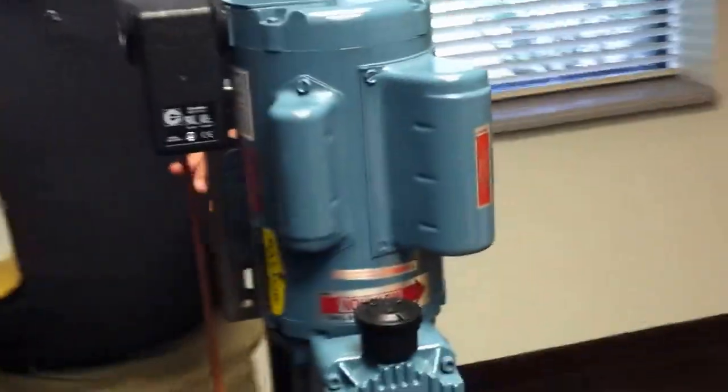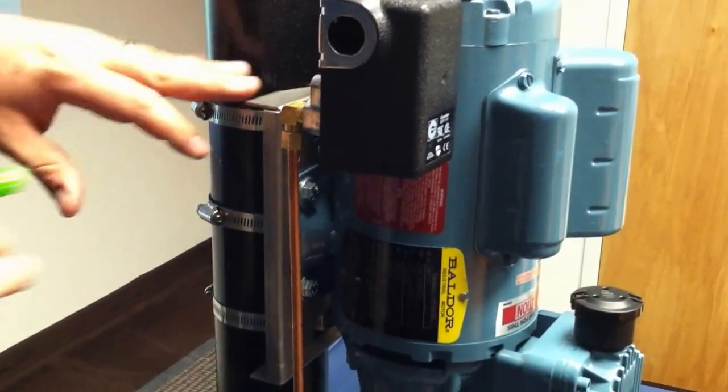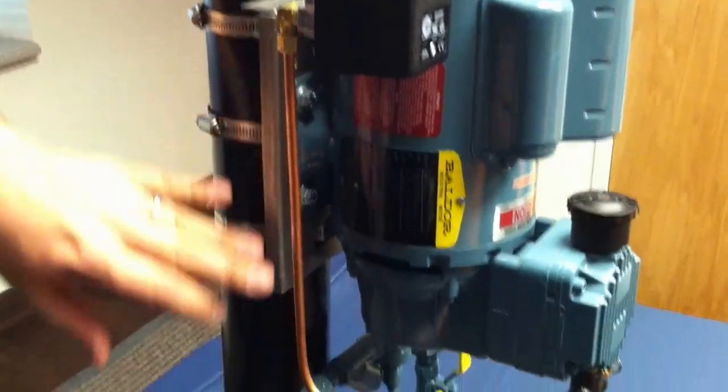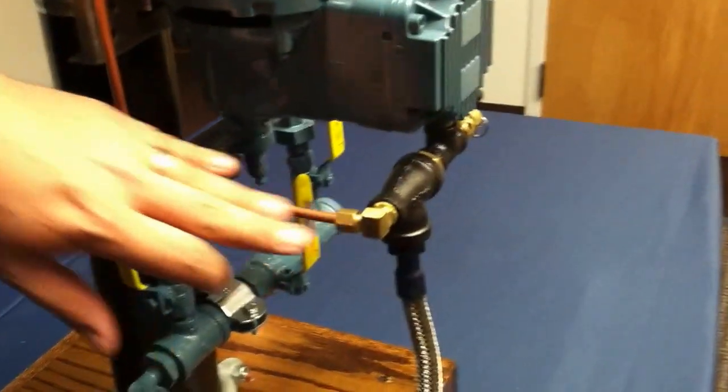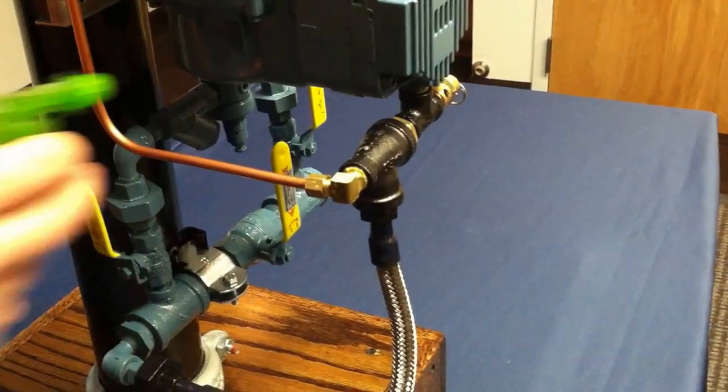First thing you do is take your soap bottle and spray every joint and union between the end of the pressure switch here through the T up here. You want to make sure that you get the check valve here as well as the safety valve over here.